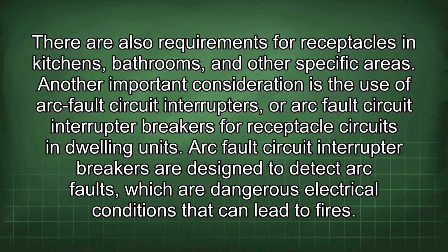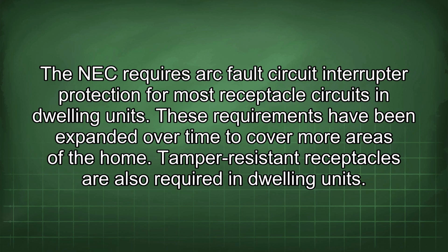Another important consideration is the use of arc fault circuit interrupter breakers for receptacle circuits in dwelling units. Arc fault circuit interrupter breakers are designed to detect arc faults, which are dangerous electrical conditions that can lead to fires. The NEC requires arc fault circuit interrupter protection for most receptacle circuits in dwelling units. These requirements have been expanded over time to cover more areas of the home.